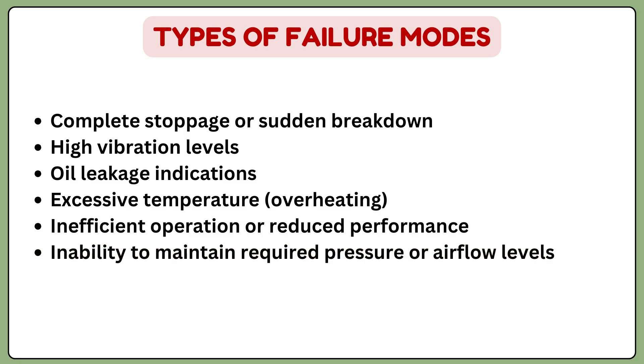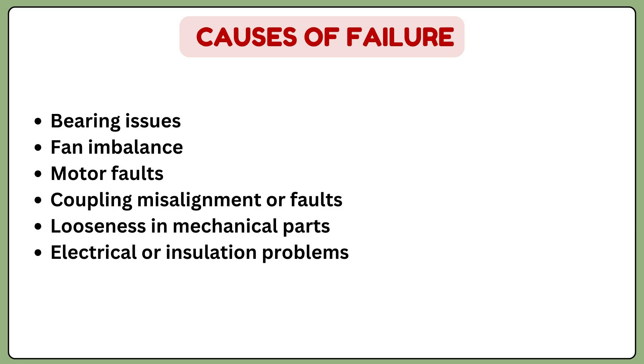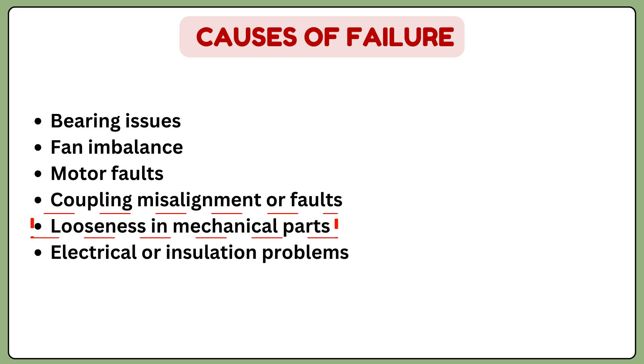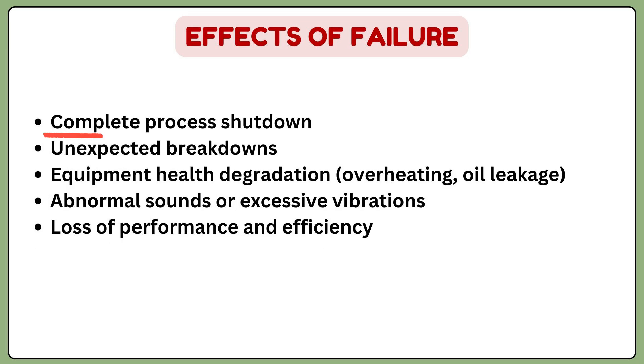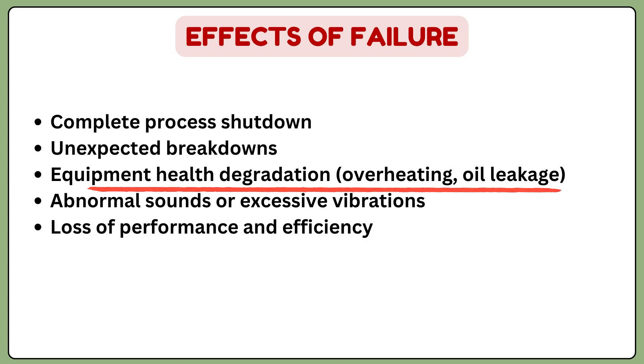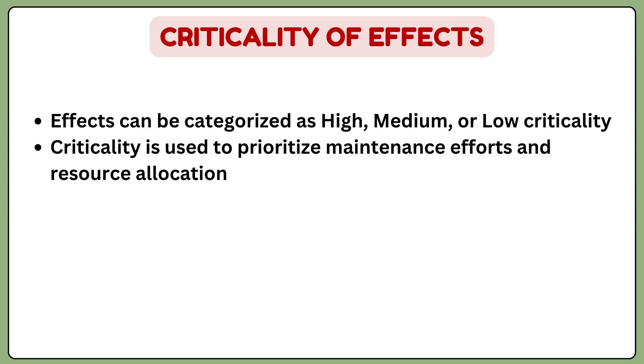The third question covers causes of failure: issues related to bearing problems, unbalance, motor fault, coupling fault, or looseness — there can be multiple causes. These causes lead to effects, which is the fourth point. The effects may include the entire process stopping, sudden breakdown, or equipment health issues like overheating, high vibrations, oil leakages, and abnormal sound. The fifth point addresses how critical these failure effects are — whether high or low criticality — and we mark the criticality level accordingly.